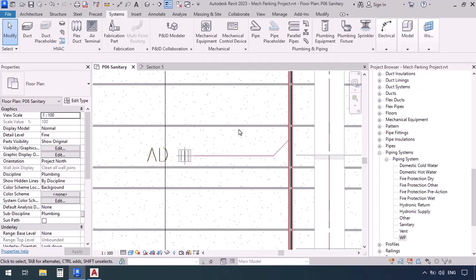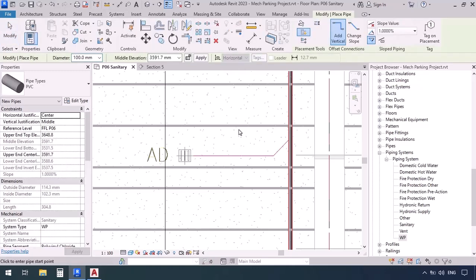We're going to activate the pipe command PI. First we're heading to the pipe types, then the system type, then the size of the pipe. But what should we do about the elevation? Our main pipe had a slope, so we don't have a precise elevation to give to this junction. Therefore, we can use the Inherit Elevation command.